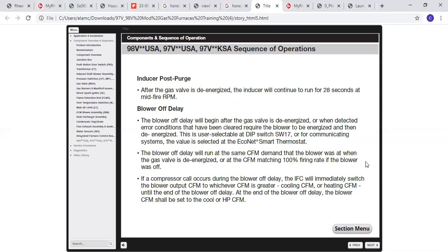Inducer post-purge: after the gas valve is de-energized, the inducer will continue to run for 28 seconds at mid-fire RPM. After that, the blower off delay will begin after the gas valve is de-energized, and when detected error conditions that have been cleared require the blower to be energized and then de-energized. There is a user-selectable DIP switch, SW17, or for a communicating system, you change that in the EcoNet Smart Thermostat.